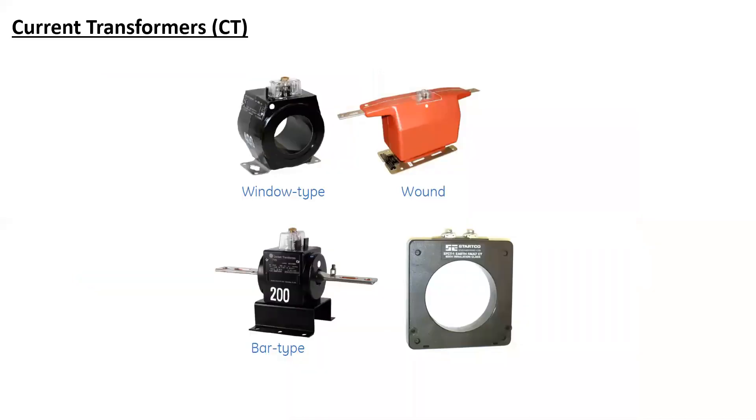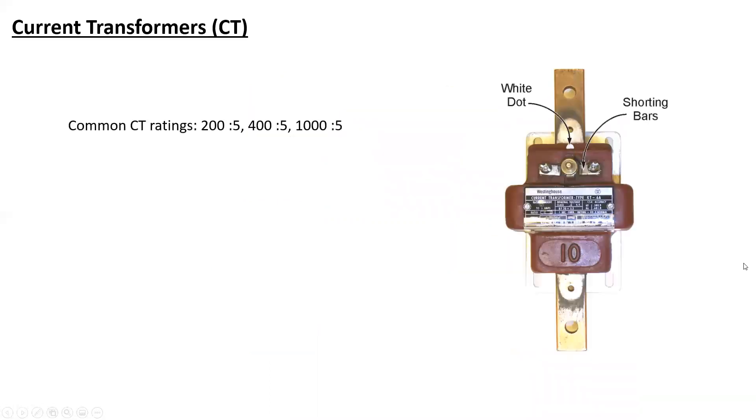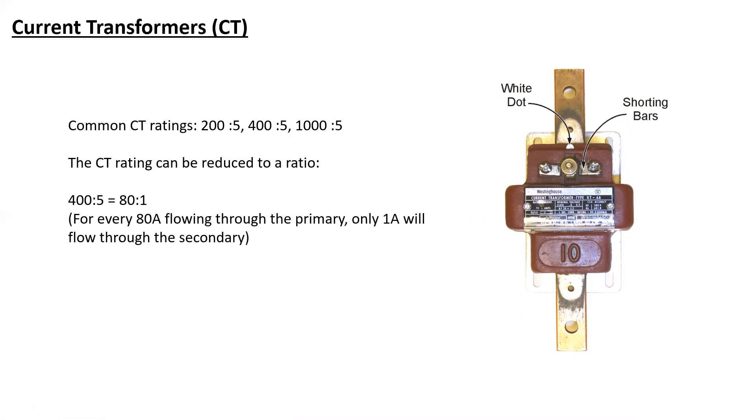There's lots of different types of CT forms out there. Bar type, window type are the most common. Window type, a lot of people will be familiar with this style where you really can just mount it wherever and it hangs on the conductor sometimes. Common ratings are 200 to 5, 400 to 5, 1000 to 5. And what that's in reference to is how many amps would be flowing on the bar and how many amps would then be present on the secondary. So, a 400 to 5 would mean it has a ratio of 80 to 1. Now, CTs are kind of interesting transformers, because their output is always rated at 5 amps, always.